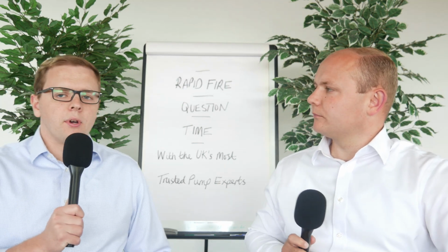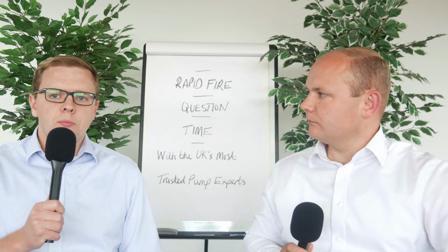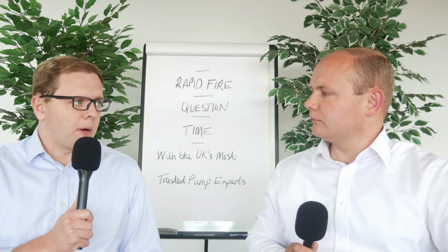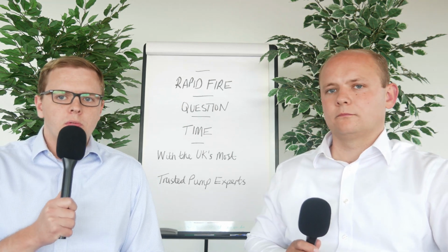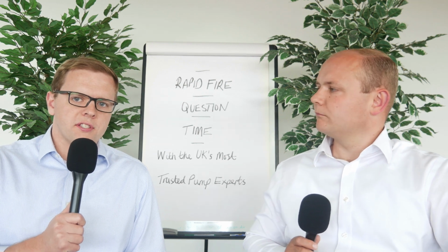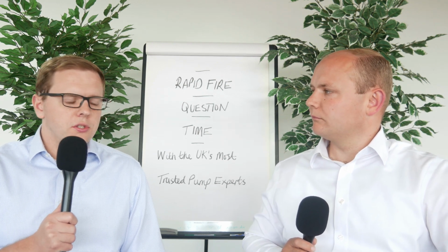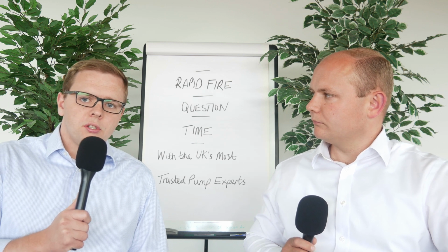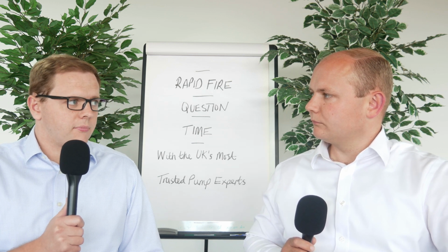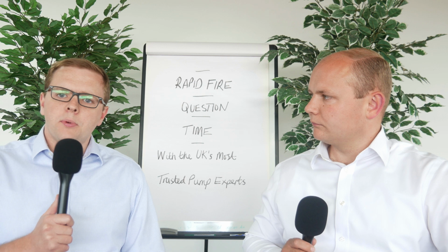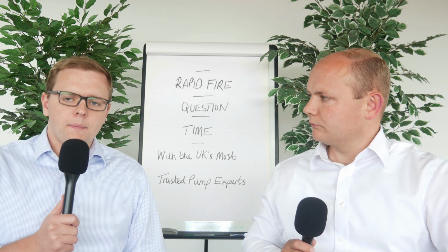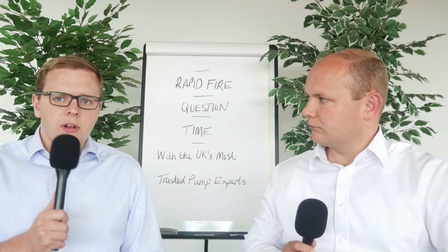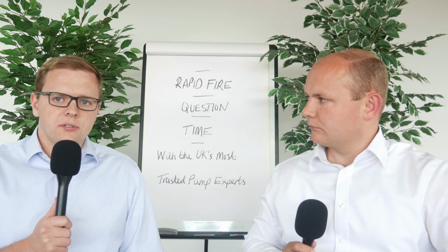So a duty standby system is a two-pump system where each of the pumps can do the full required flow of the system. A duty assist, on the other hand, requires two pumps to do the complete flow of the system.